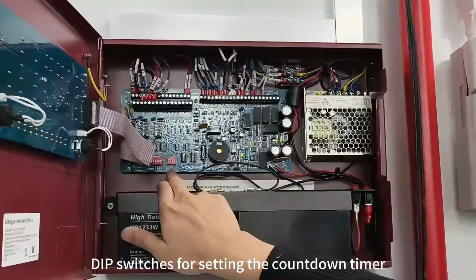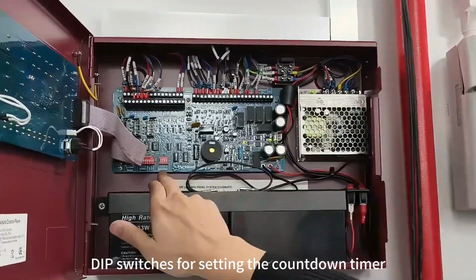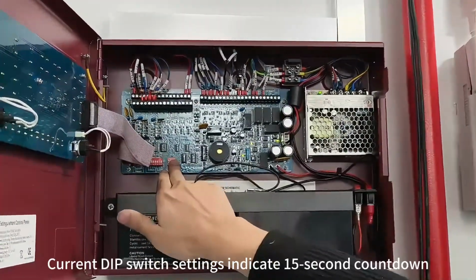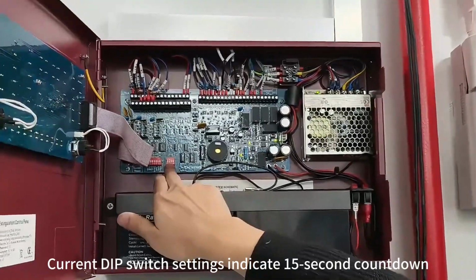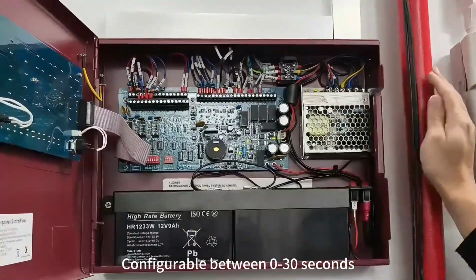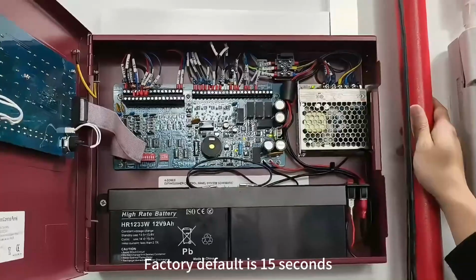Here are the dip switches for setting the countdown timer for fire gas injection. Current dip switch settings indicate a 15-second countdown, configurable between 0 and 30 seconds. Factory default is 15 seconds.